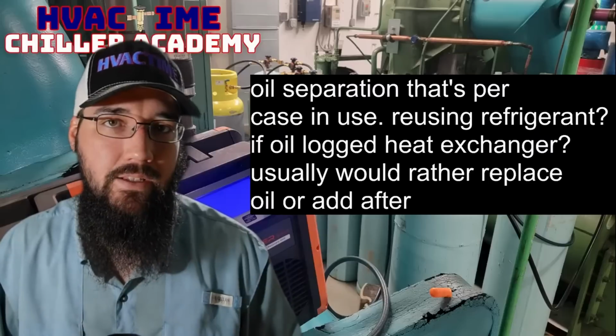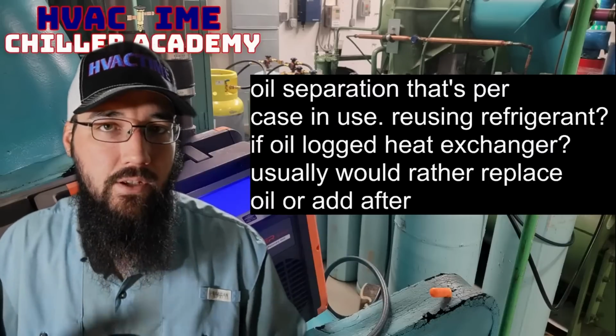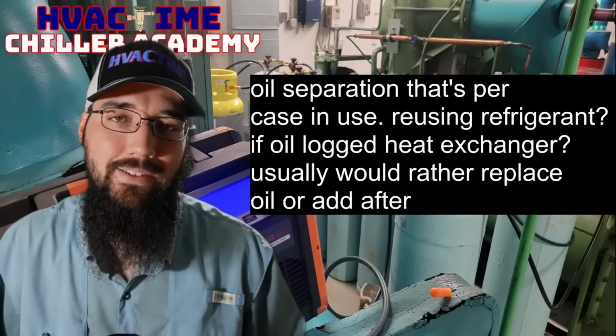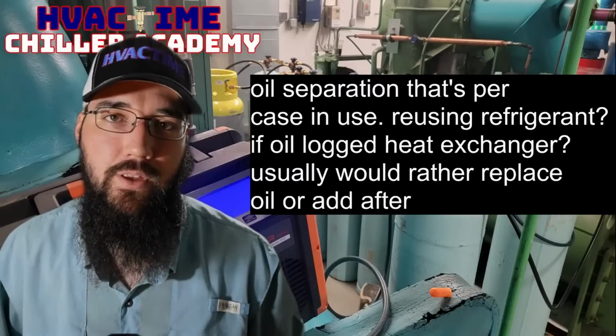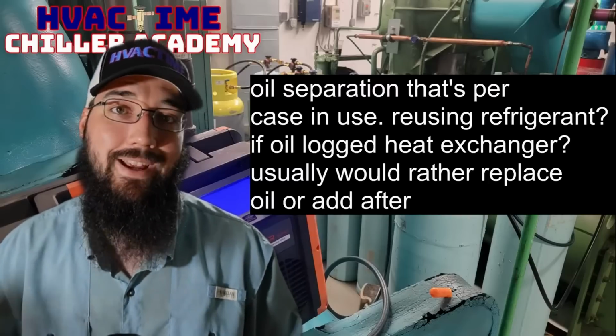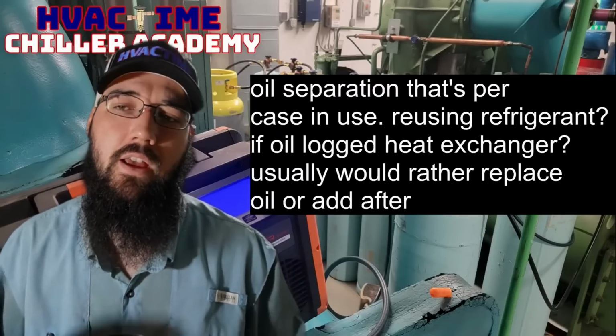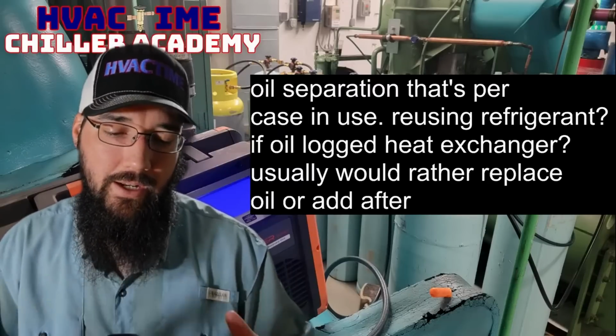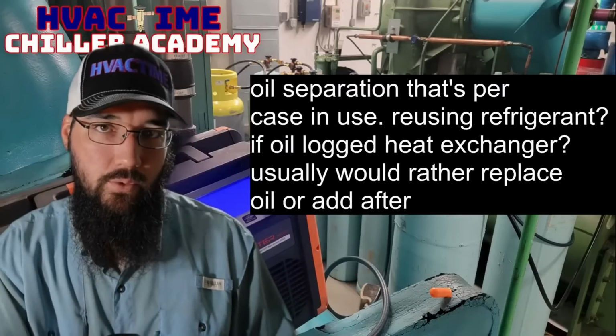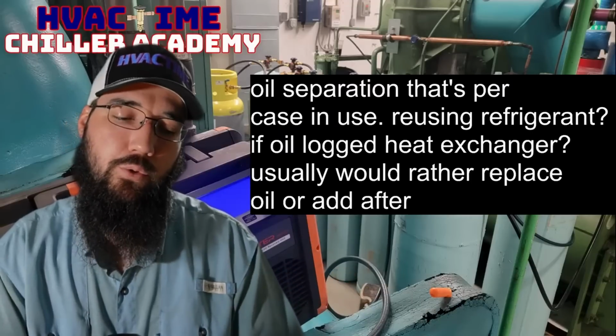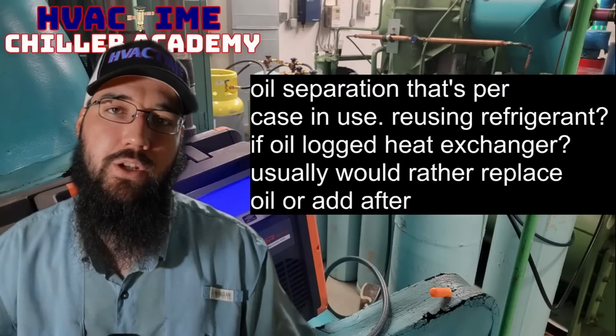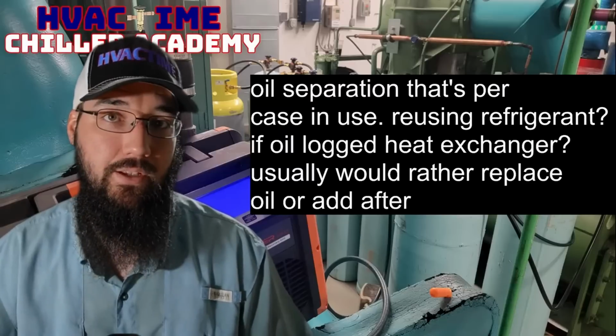Now, if you can get the machine online, even if just for a short time, try to get some of that oil back. A way to do that, if you had a severe migration event, is to add just enough oil into the sump to allow the machine to come online safely.